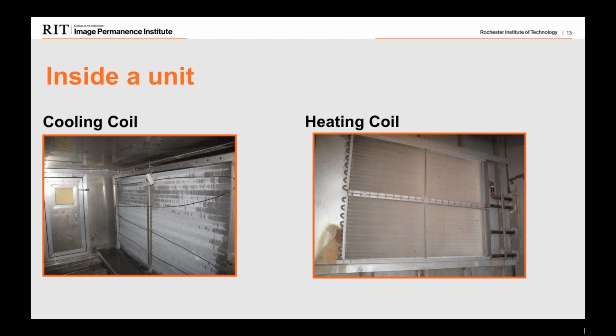If possible, it will dehumidify. That's dependent on the dew point of the air passing over the coil and the capabilities of the coil. Not every cooling coil will dehumidify all the time. One way to identify a cooling coil, if you're looking in here, is via the condensate tray, which is underneath the coil. It's to catch the water if it condenses and remove it from the unit. And then there is your heating coil, which would be the image on the right. Again, that's a tube and fin, but they can also come in electric style, which would be similar to a toaster heating coil, which would run back and forth across the airstream. And obviously the heating coil would have no condensate tray.